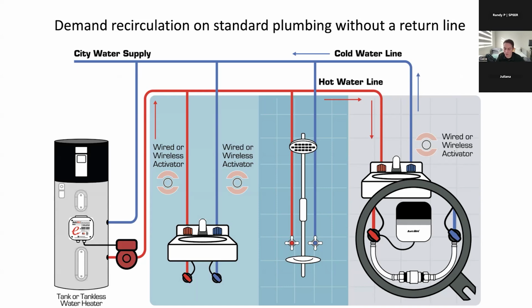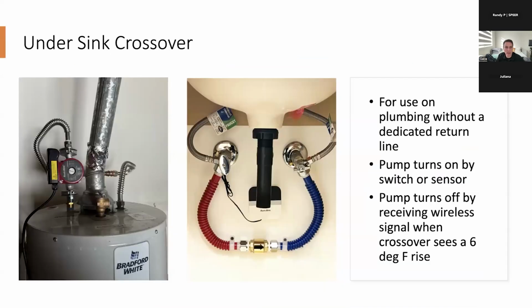Now, I'll show you guys the actual language in IECC. So this is our version of it. It's called the undersink crossover, where we can go into a house without a return line and just cross connect the hot water line into the cold water line. The pump turns on based on sensing demand, and then the pump shuts off once the temperature sensor sees about a 6-degree rise in temperature. It sends a wireless signal back to the pump to shut off.